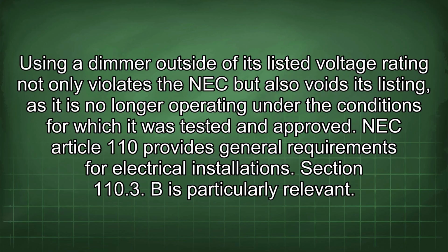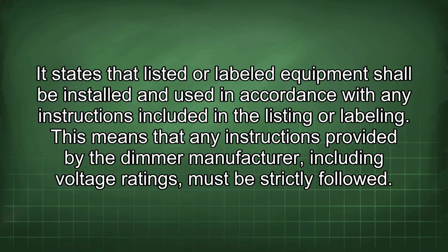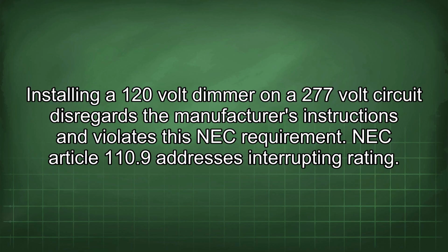NEC Article 110 provides general requirements for electrical installations. Section 110.3 is particularly relevant. It states that listed or labeled equipment shall be installed and used in accordance with any instructions included in the listing or labeling. This means that any instructions provided by the dimmer manufacturer, including voltage ratings, must be strictly followed. Installing a 120-volt dimmer on a 277-volt circuit disregards the manufacturer's instructions and violates this NEC requirement.